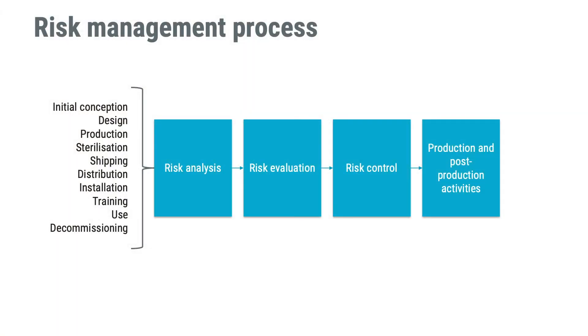If you develop or manufacture medical devices you need to work with risk management. Risk management is not only relating to the use, design, and manufacturing of a medical device — you need to have a risk management process that covers all life cycle phases from initial conception to decommissioning or scrapping. This means you should include risks arising from poor design, failure in production processes, rough handling during shipping, misuse by a user, failure in sterilization, component failures, and risks arising from decommissioning. All those risks should be taken through the complete process of risk management and be documented.